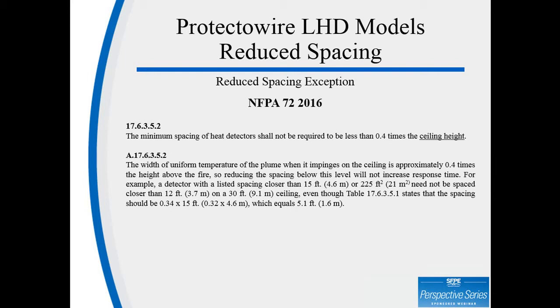The justification for this is in the appendix. I'm not going to read the whole thing, but the width of uniform temperature of the plume when it impinges on the ceiling is approximately 0.4 times the height above the fire. So reducing the spacing below this level will not increase the response time.